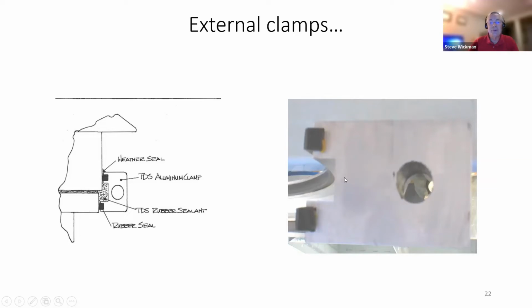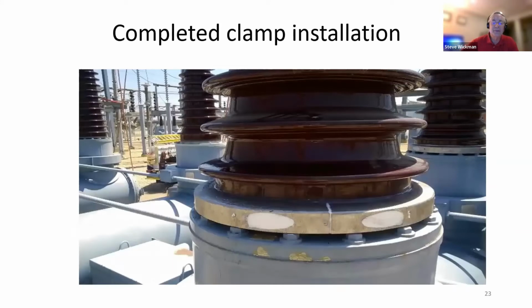And here's an actual photograph of a clamp in that same orientation where that would mount onto that porcelain steel interface. Here's a completed clamp. In this case here, instead of having the ears that stick out where the bolts go to hold it together, this one had a recession that a threaded rod with nuts goes into to pull the two halves of that clamp, and we just fill that with an RTV type caulk to just fill that cavity, make it look a little bit better, keep the spiders and moisture and such out of there. And we'll also shoot a bead of RTV sealant around the perimeter at the top of the clamp when it's accessible like this, just to minimize moisture intrusion into there.